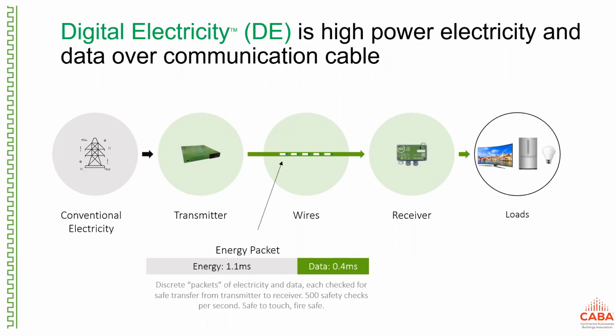The important thing is that the space between the transmitter and the receiver is rated as a Class 2 circuit in North America, so it runs in communication ducts, the same space where you're running your Ethernet cables. This technology, even when transferring many kilowatts of power, installs with the same practices as Ethernet cable.